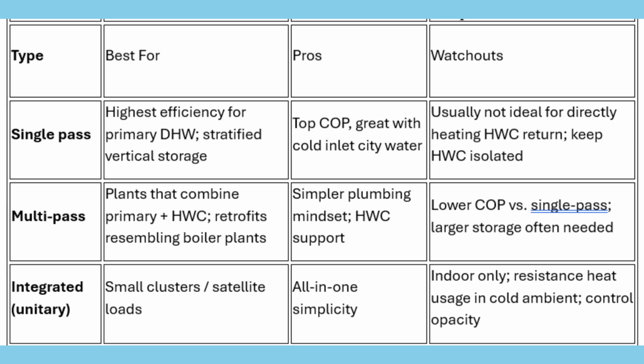Integrated or unitary models package the heat pump with a tank and backup element. They shine on small satellite loads or clusters, typically indoors. For most multifamily centrals, use single-pass for primary heating. And if you need dedicated temperature maintenance, use a small multi-pass unit for the loop.